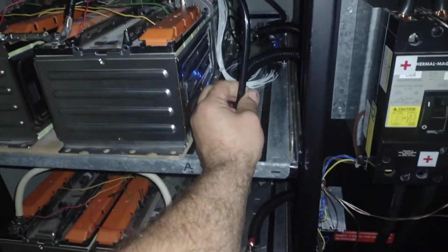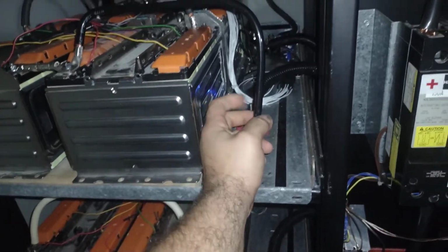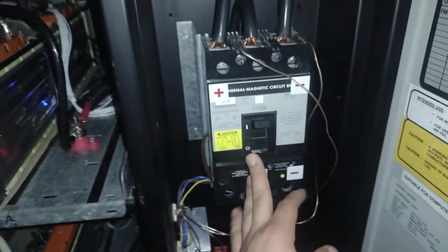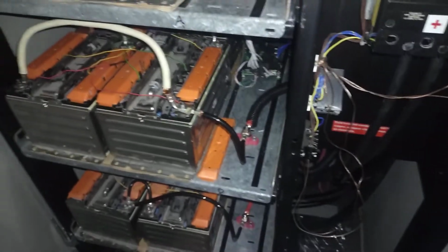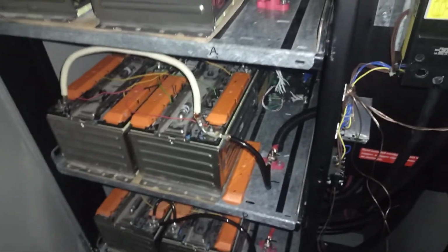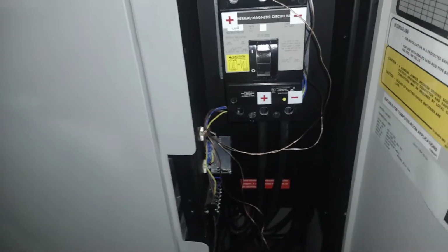But in reality, I typically only see like 45 amps to each one of these, which is fine because this is a 150 amp breaker, and that's typically only when I see it charging. As the tag said, it was only 137 amps for pulling from the inverter, but when it's charging, I've even seen up to 50 amps on each one of these.